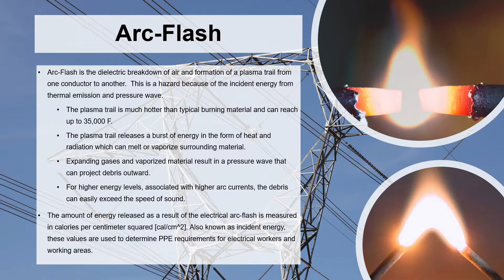You have your conductors: negative in blue, positive in red. There's a potential difference between those two conductors. You could also have a potential difference between the line and ground, ground being neutral, so there's a voltage there. So when I say potential difference, I mean voltage. You have a line-to-line voltage and a line-to-ground voltage. Those could both potentially be sources of electrical arc flash hazard.